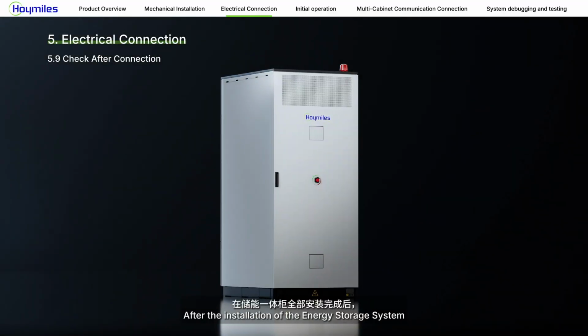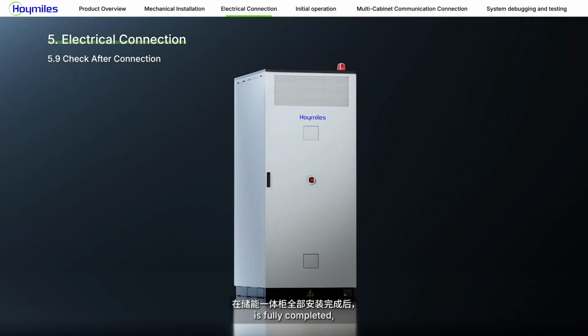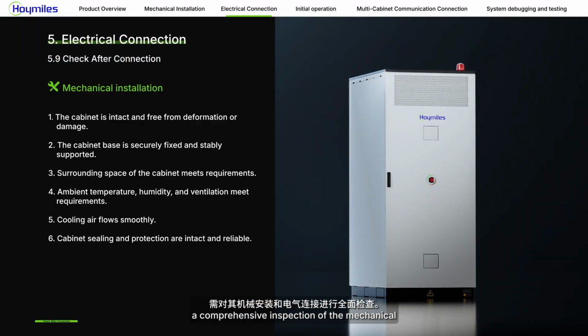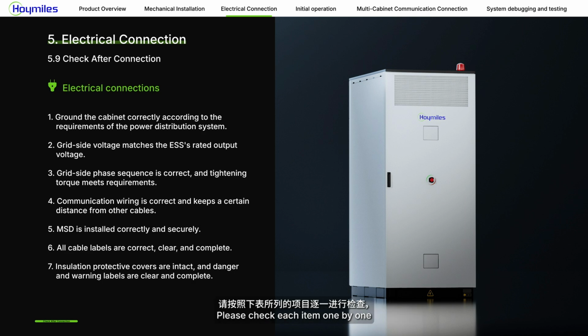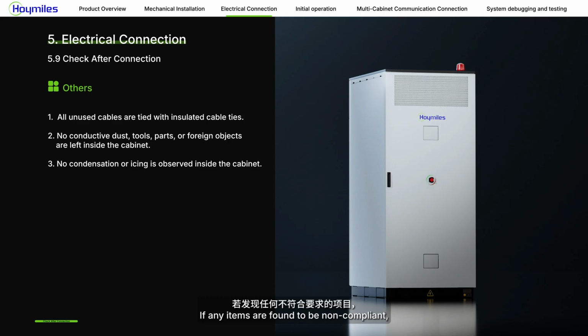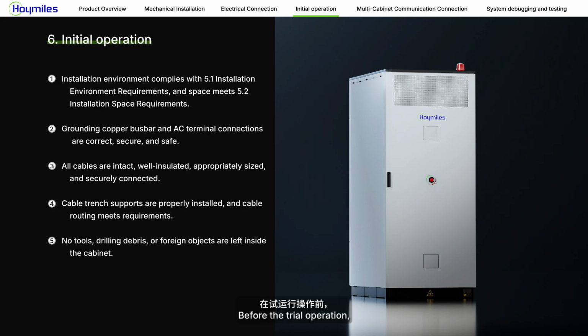After the installation of the energy storage system is fully completed, a comprehensive inspection of the mechanical installation and electrical connections shall be carried out. Please check each item one by one according to the items listed in the table below, and make detailed records during the inspection process. If any items are found to be non-compliant, corrective actions shall be taken immediately. Before the trial operation, please perform the following checks.